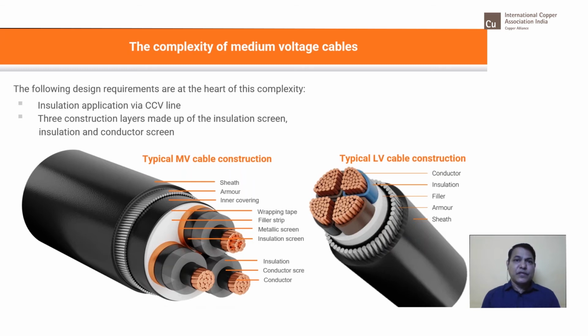Construction conductors are circular, as I said. Sharp edges are not allowed in a sector shape. You tend to receive that sharp edge, and in medium voltage cable, due to the high stress or high voltage, they need to have a uniform surface. That is one of the reasons that they are circular.